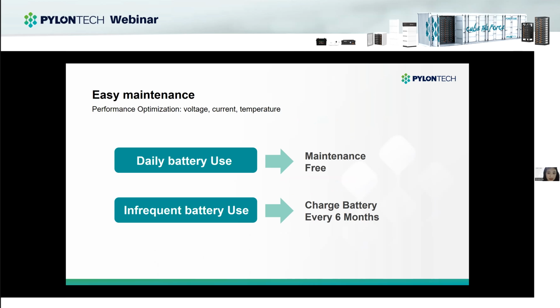Our batteries are easy to maintain as long as they are used normally. There will generally be no problems if you use the right inverters and all the settings are right. If you use the batteries every day, they are maintenance free. But if you don't use the battery regularly, for example, you are always away from home for a long time and do not use the battery during that time, then the batteries need maintenance. For better performance, remember to fully charge the battery system every 6 months.